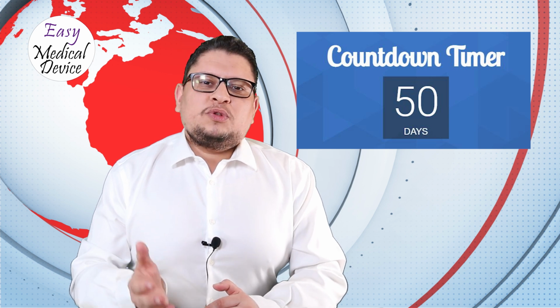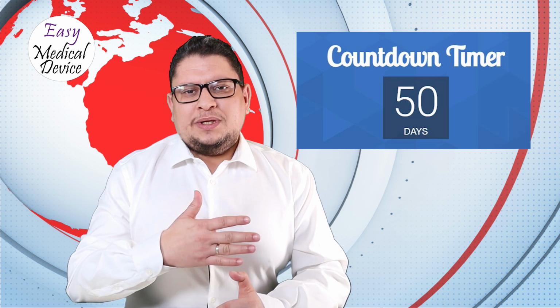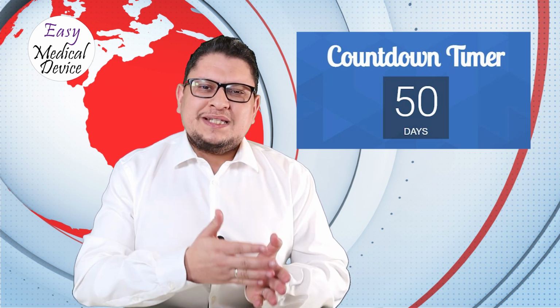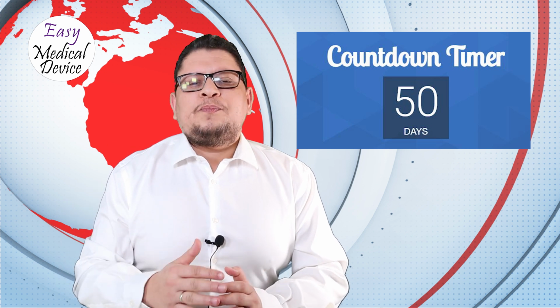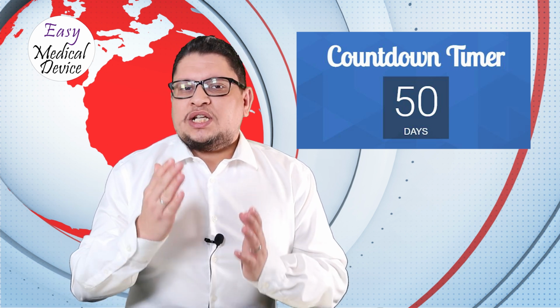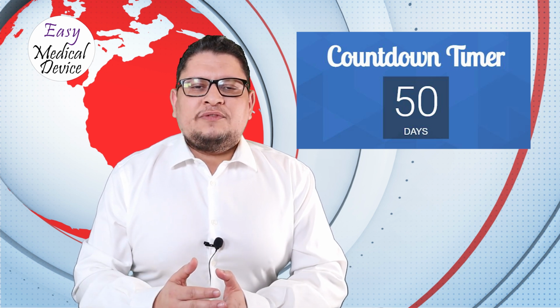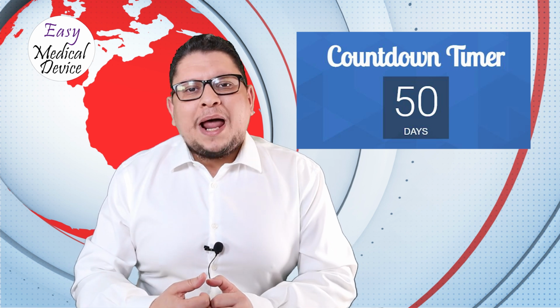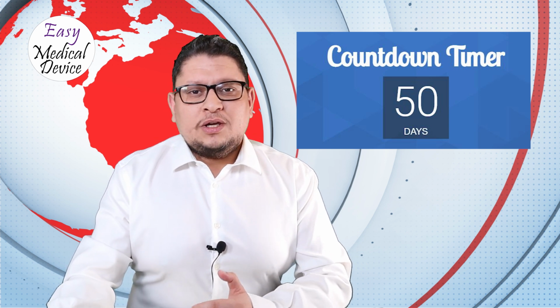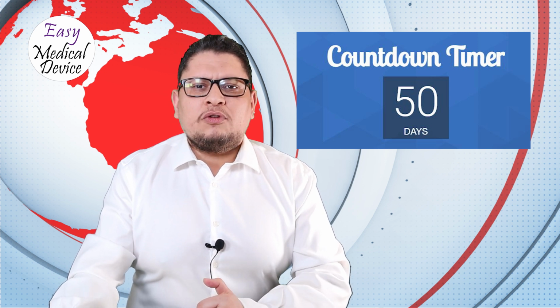And something we also talked about in the previous podcasts: if you have a significant change during that transition period between the 26th of May 2021 and the 26th of May 2024, then this significant change can completely stop your transition. As soon as you apply this significant change, you have to apply the EU MDR. So that is why you really have to plan for it. It's not something that you just guess, oh, will we have a change or not? No, you really have to plan for this kind of thing.